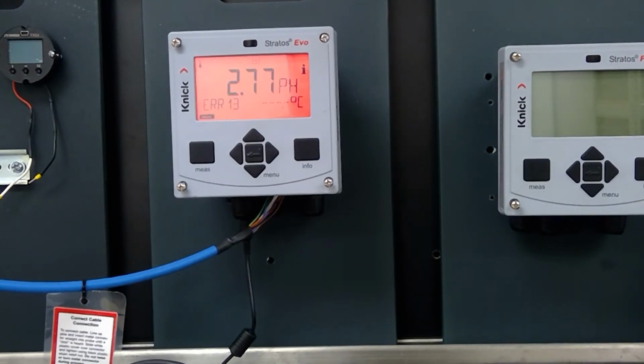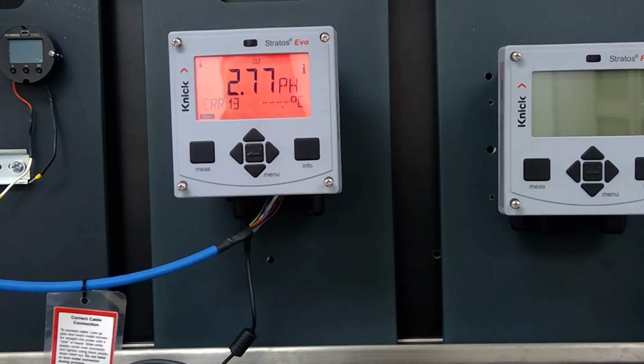Now, for those of you who want to do this calibration on process, that's fine. You just allow the process to hydrate the sensor. So you just need to come back after a period of time. Again, we use 24 hours as our basis, and do a process calibration. And the electrode will be calibrated, and you won't have to worry about any drift.